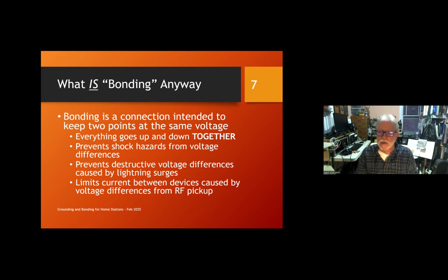It also limits current between devices. When you pick up RF from your local signal, or you have a transmitter nearby or something, and when you've got everything bonded together, that means the voltage difference is minimized, and that means the RF current flowing is also minimized. And that's what causes RFI. It's not the voltage, it's the current getting where it should not be. So if you can minimize the current, you can minimize your RFI, and you do that by bonding. So bonding is an important part of station design.